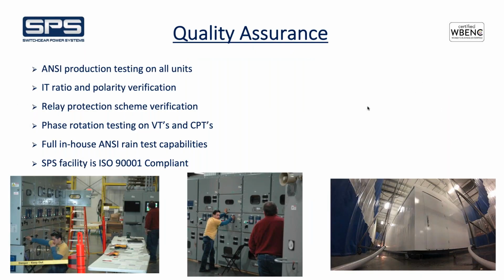In terms of quality assurance, many of the same tests that we would perform on draw-out metal clad switchgear, we're obviously going to verify instrument transformer ratios and polarities, go through the relay schemes. We also have a full indoor rain test booth, so all of our outdoor equipment is rain tested prior to shipment, and we are ISO 9001 compliant.